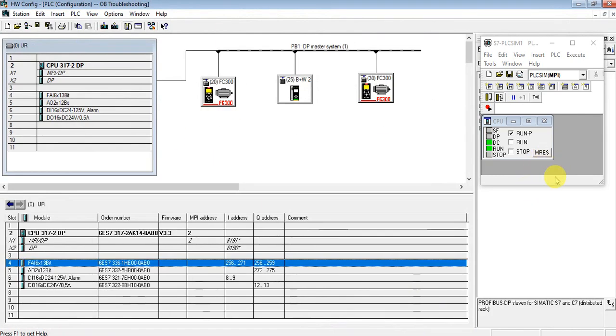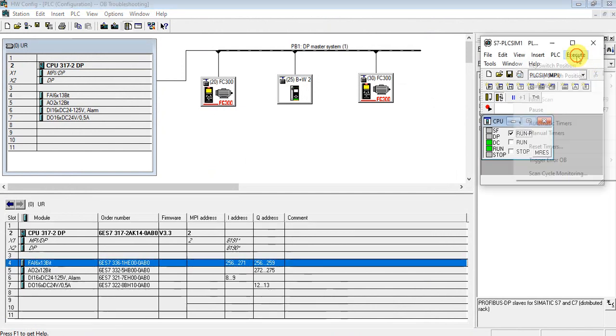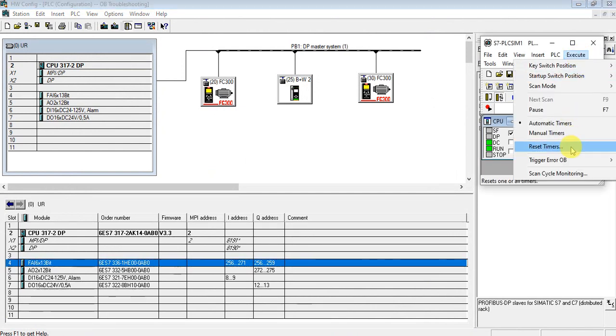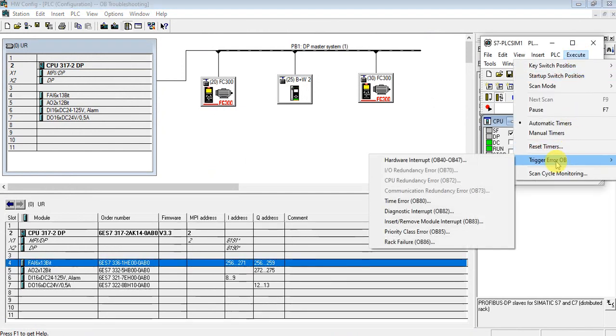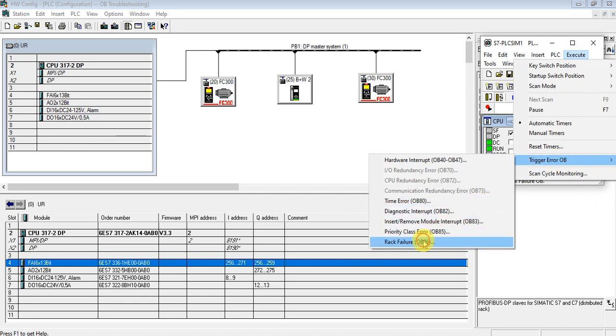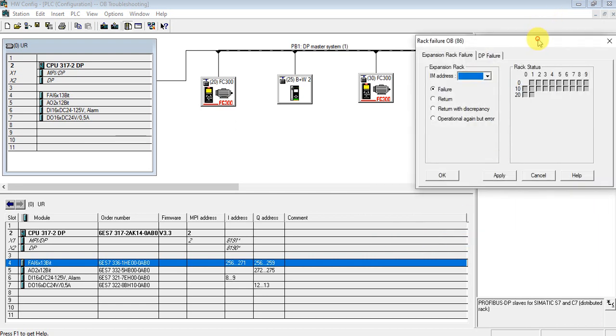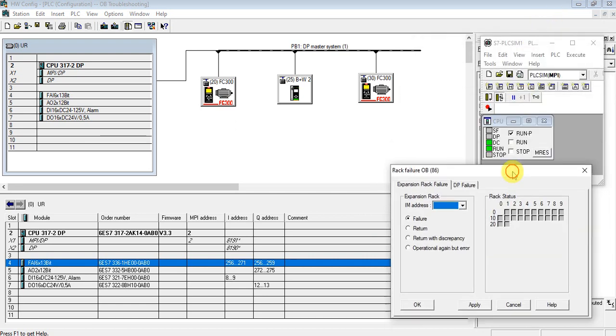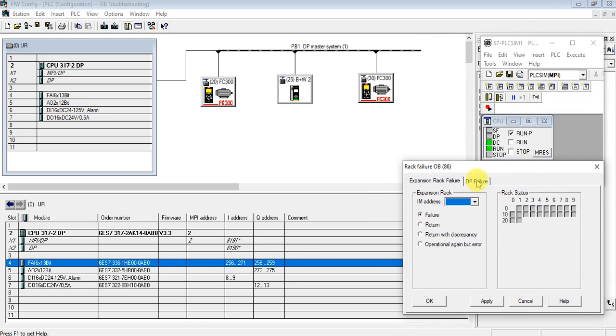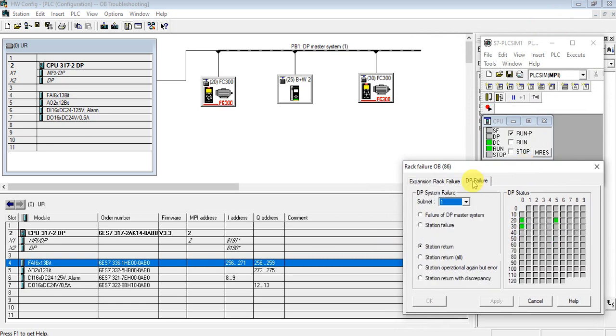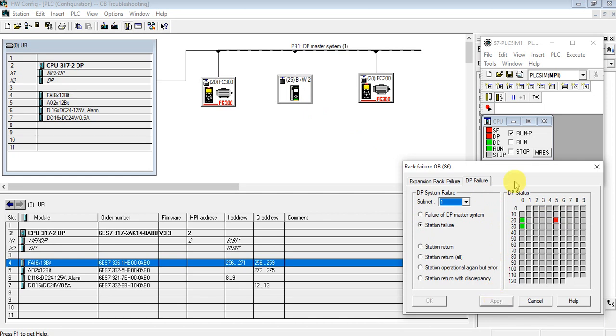Let's get an error again with OB86 and let's see what happens. Let's make slave address 25 missing. As you see the CPU shows some system fault in the DP fault or Profibus fault but it doesn't go to the stop mode, it's executing the other programs.